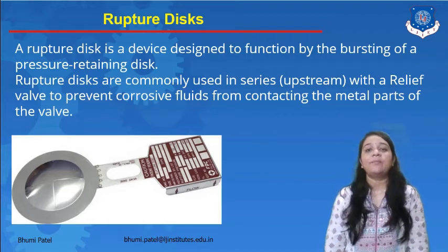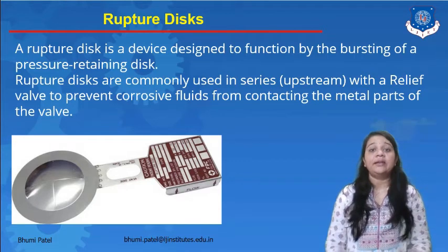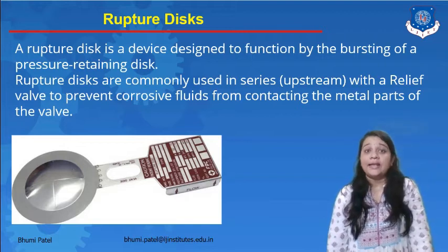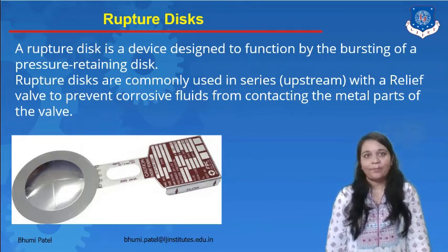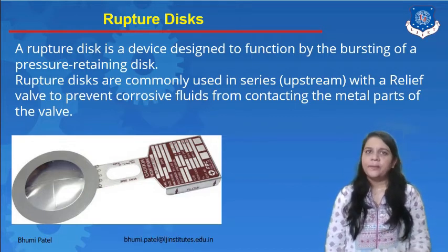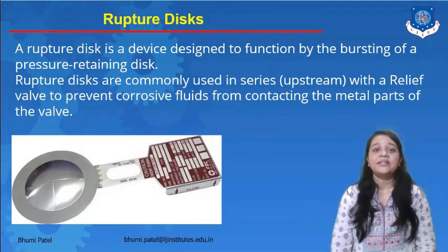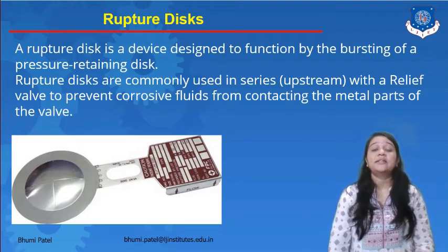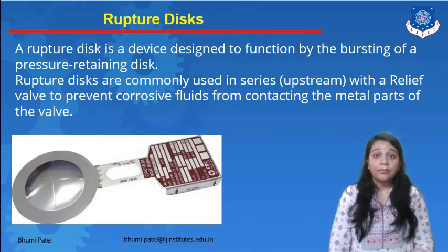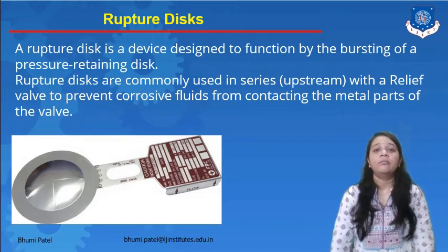Now a rupture disc may be used either in primary relief or in secondary relief, and it is connected in series with the relief valve or for other functions like the quick opening valve. The first one is the primary relief rupture disc. It is used for primary relief, where the rupture disc is the only device utilized for pressure relief. As such, it has the advantages of being leak tight with instantaneous response time, and it has minimum pressure drop, lower cost, very high reliability and minimum maintenance.